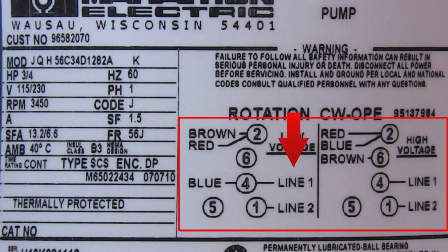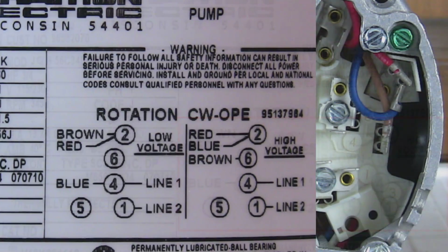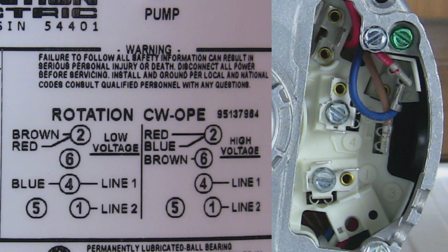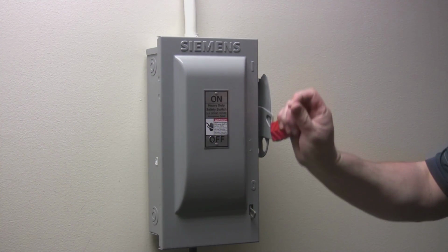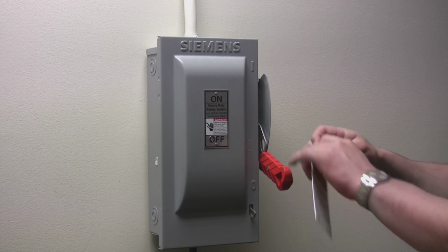The wires from the machine are labeled as line 1 and line 2 because they could be different colors depending on application. A ground wire is not typically called out in these diagrams because it is assumed technicians know this is a legal requirement. Wiring of the motor is completed by following the diagram. To do this safely, follow these steps. Number 1. Disconnect power from the machine and use proper lockout-tagout procedures.